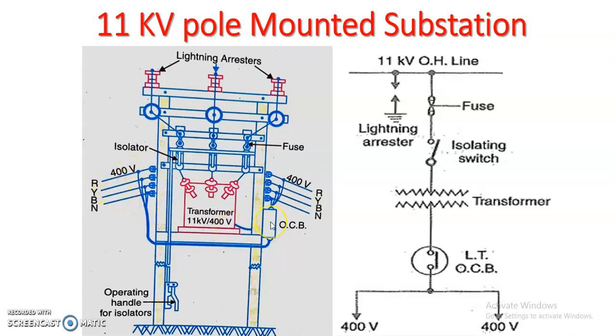Here we are using an oil circuit breaker in order to protect against faults. If a fault occurs at the consumer end, that oil circuit breaker will protect the transformer from that fault current. Here we are using an operating handle for the isolator so that the isolator can be manually operated, that is, the circuit can be opened or closed.